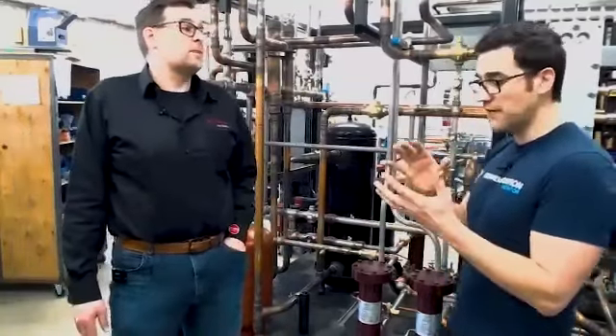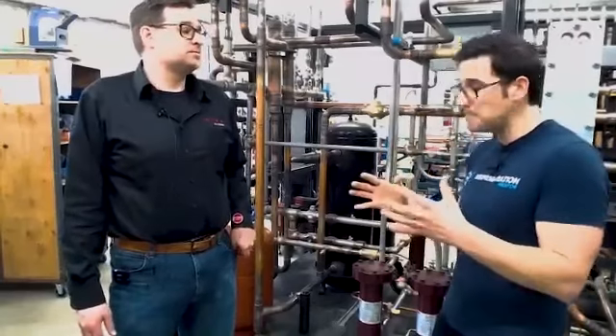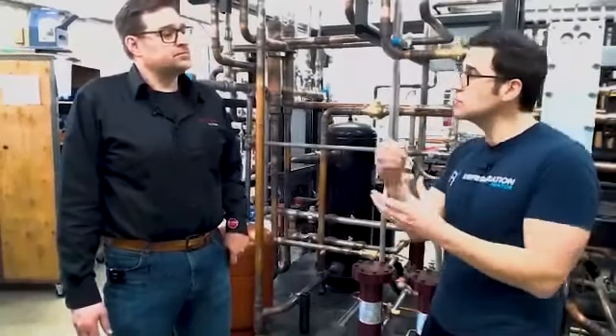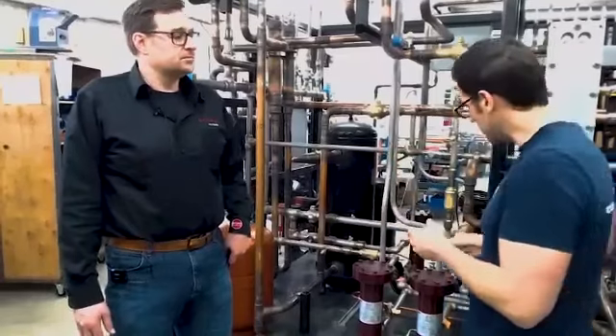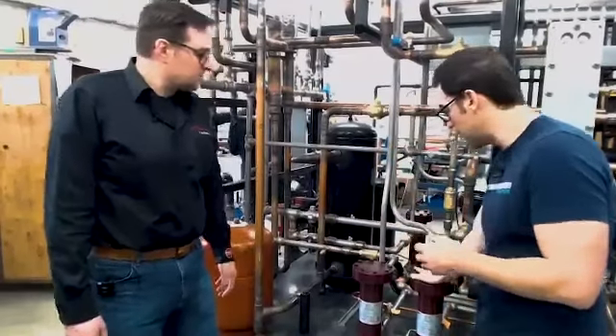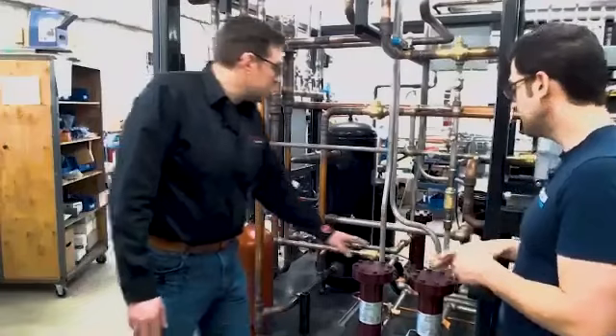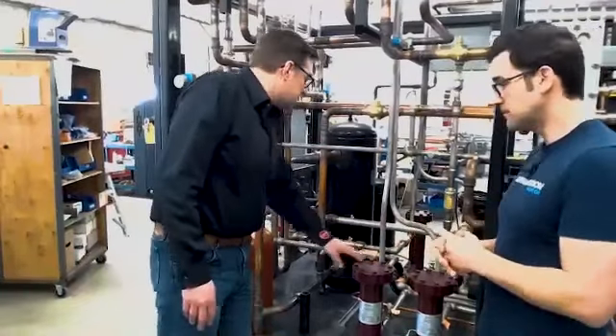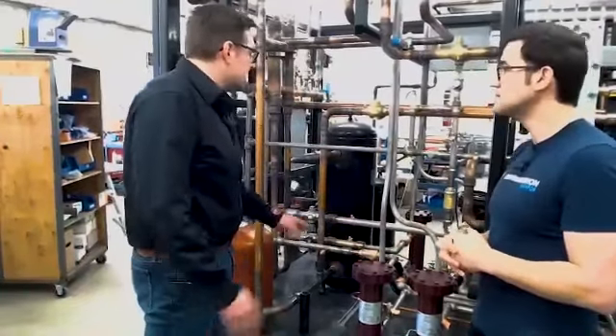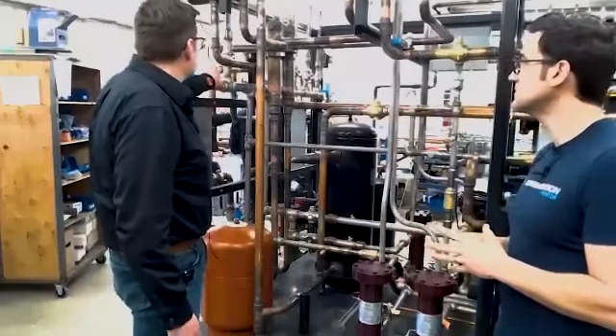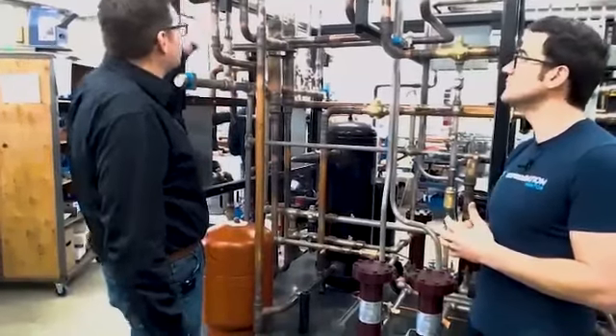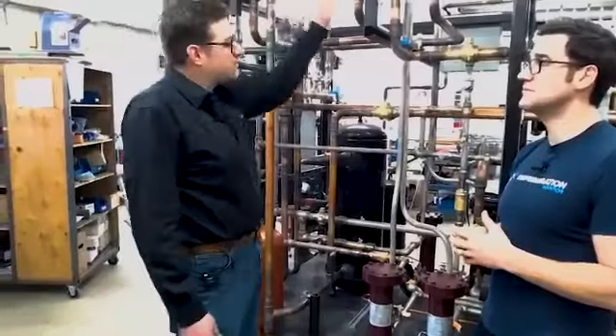Let's start from the beginning. Your compressors start up and begin to move CO2, high pressure gas, which comes into the oil separator. What's the next step? In this application, if we have heat reclaim, we go through that first, but the end result is always the same: we go into a manifold, and that manifold goes out into the gas cooler, then we come back from the gas cooler.